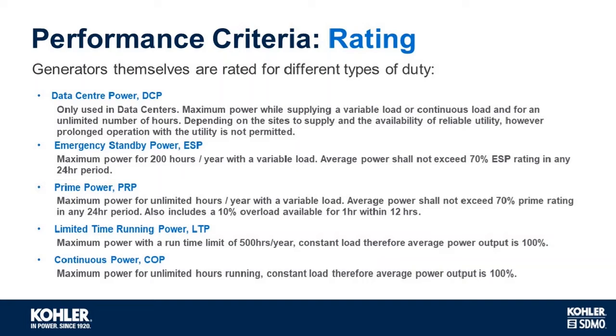Next, prime power, PRP, maximum power for an unlimited number of hours with a variable load, and the average power should not exceed 70% of the prime rating in a 24-hour period. However, it also includes a 10% overload capability for 1 hour in 12 hours.